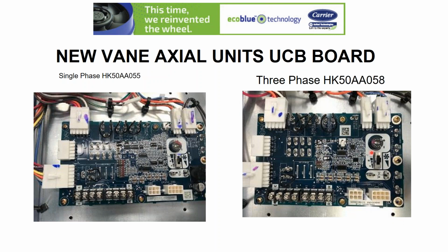As we talk later today on troubleshooting, and when I talk about some of the pins and point it out on the wiring diagram, we're going to be talking about this plug right here. So I'm going to show you points to read on the 4 leads here. You can see 2 here, there's 2 underneath, and in conjunction with our 2 pins here in order for troubleshooting. Basically what we're doing in that troubleshooting scenario is verifying that we do have 10 volts DC from the motor, and that we are getting the correct or desired 0 to 10 volt DC output back out to the motor. And then we'll talk about another harness plug that's in the fan cabinet and some other things along the way.